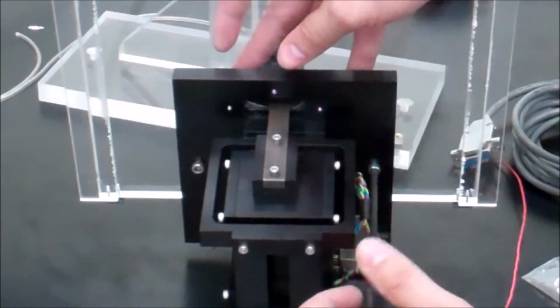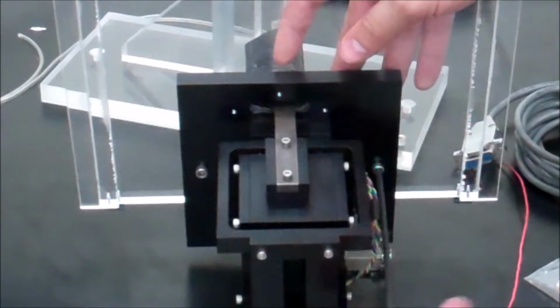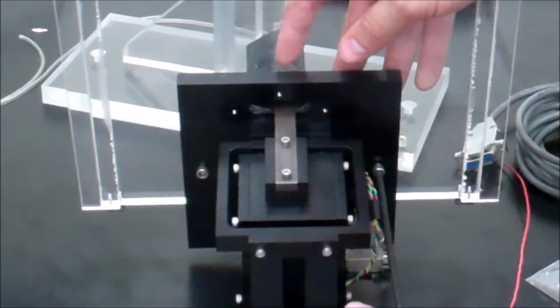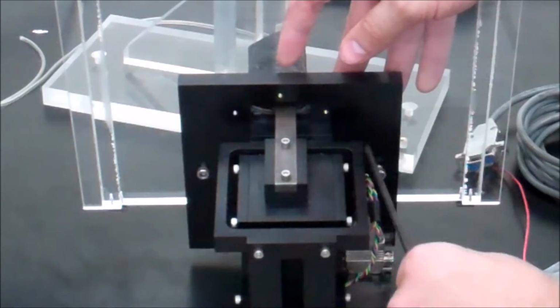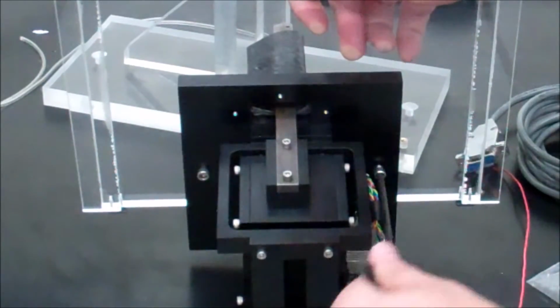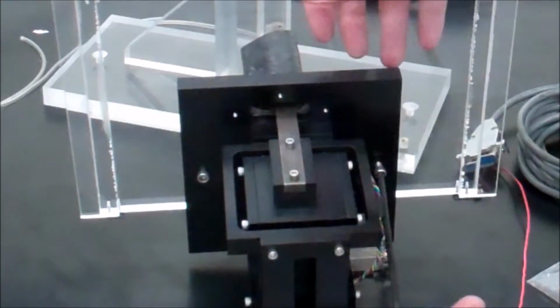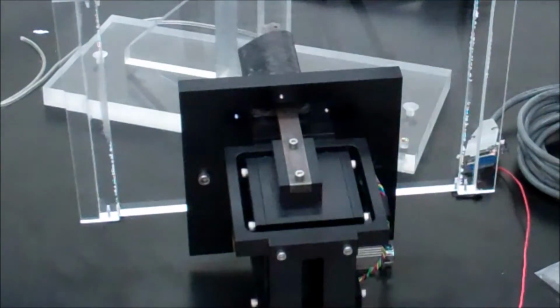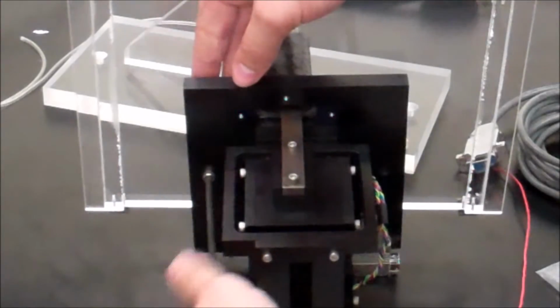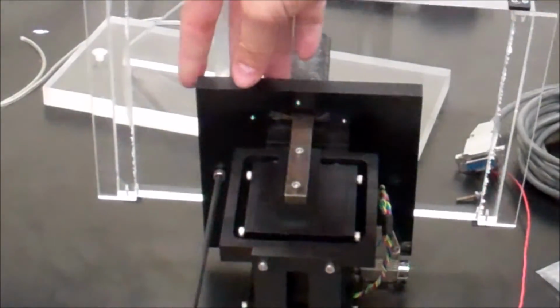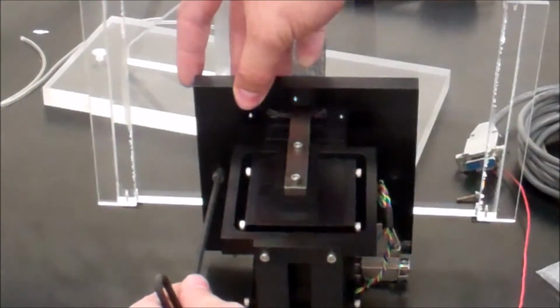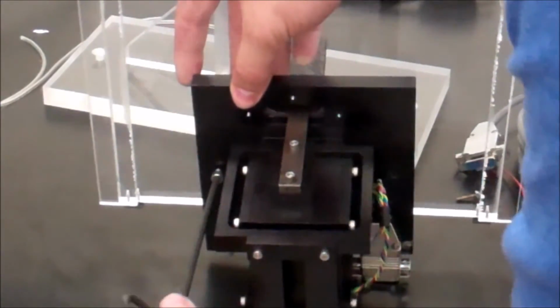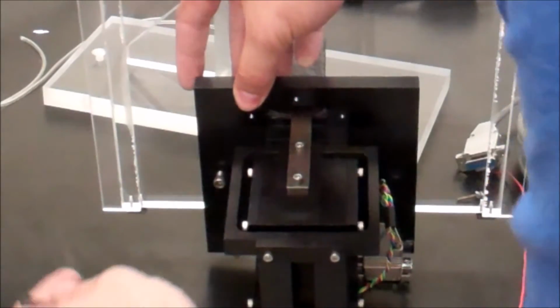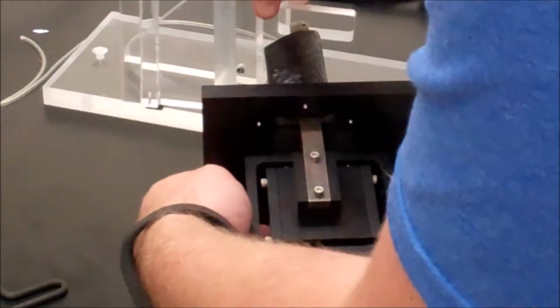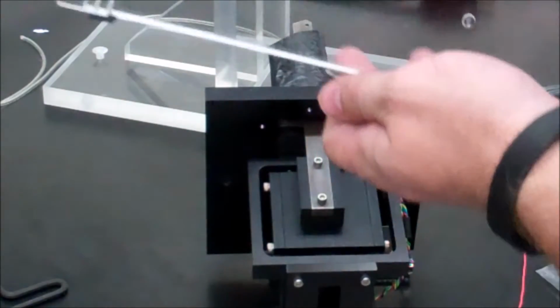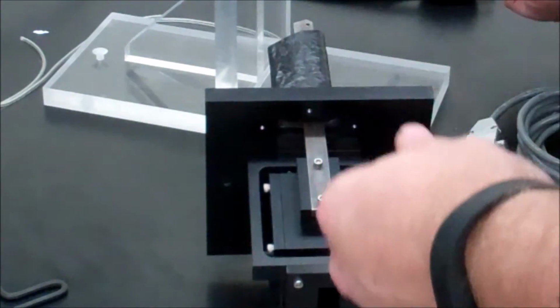You're going to put your Allen key in it and you're going to loosen that screw to separate the force balance system from the bottom test section, the acrylic section that holds it in place when you're actually using it. And you're going to set the screw off to the side for the time being because you're going to need to use it for the calibration. And then you remove the bottom piece and set it to the side.